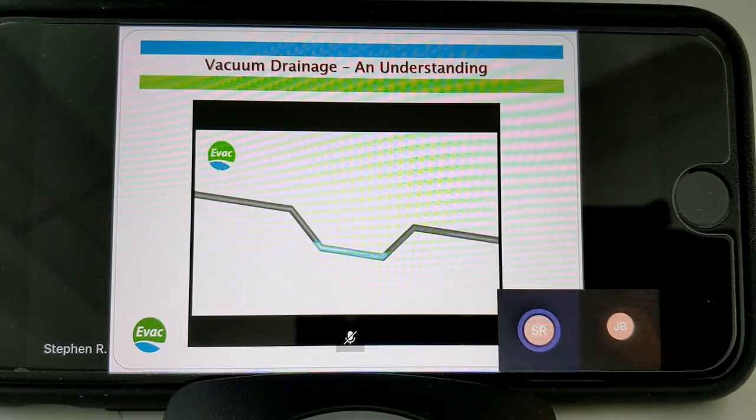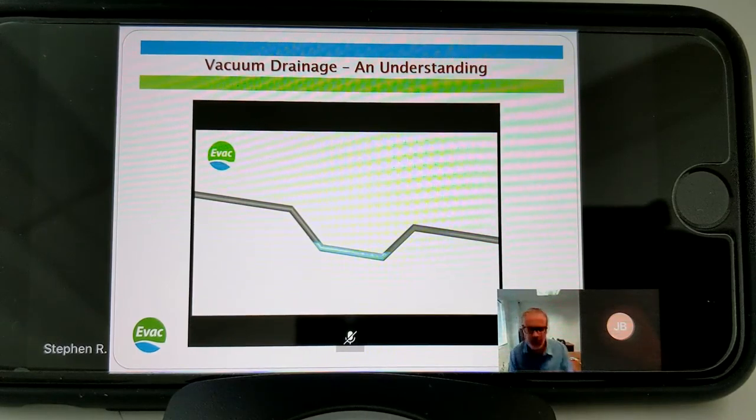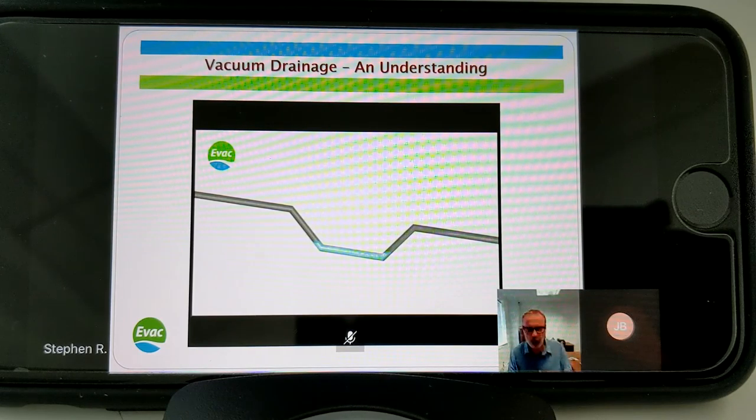The depth of the pocket will vary to suit the design. You can sometimes install a transport pocket before you've reached 25 to 30 metres - for instance after 15 metres. Why? Because the system is flexible. If a piece of ductwork is crossing your pipe and clashing with your vacuum main, you can install a transport pocket there. Whereas a standard pocket might just be two fittings butted together, if you need to step underneath a piece of ductwork you might need to make it deeper and longer - all coming back to the flexible solution that vacuum systems offer.